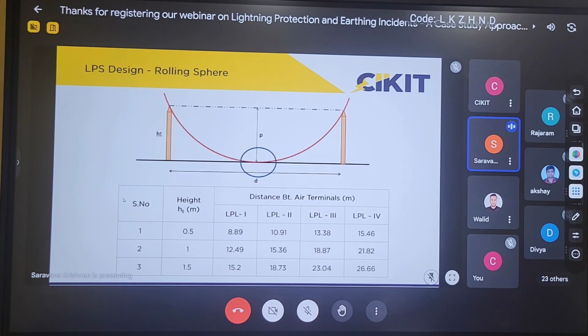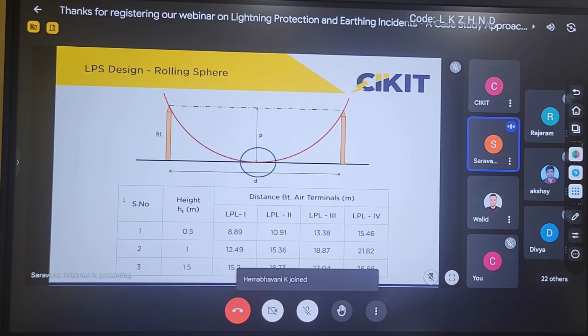If I am performing the calculation using a 1 meter air terminal and arrive at 10 air terminals, and one more person performs the calculation for a 2 meter air terminal and arrives at 5 air terminals, then both designs are correct. We cannot say that I have to go for only 1 meter or only 2 meters. It is up to the designer and the site conditions to decide the suitable height of the air terminal. The standard does not stick to any specific requirement like only 1 meter or 2 meters above the structures.